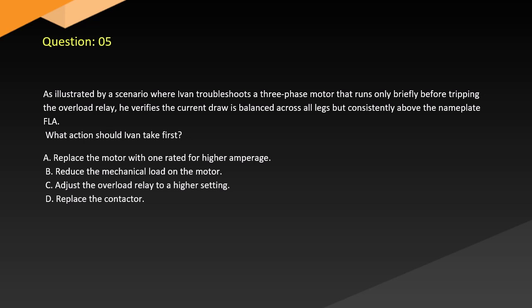Question 5. Illustrated by a scenario where Ivan troubleshoots a three-phase motor that runs only briefly before tripping the overload relay. He verifies the current draw is balanced across all legs but consistently above the nameplate FLA. What action should Ivan take first? A. Replace the motor with one rated for higher amperage. B. Reduce the mechanical load on the motor. C. Adjust the overload relay to a higher setting. D. Replace the contactor.